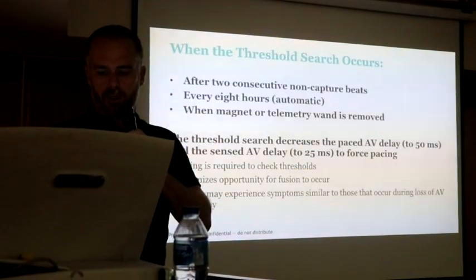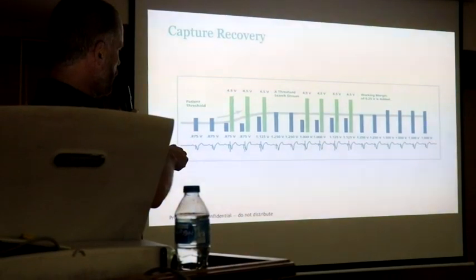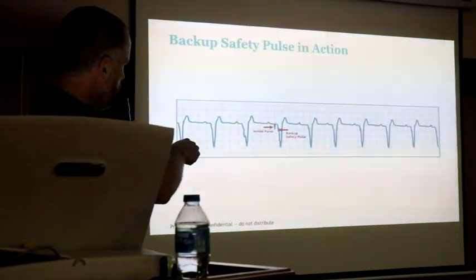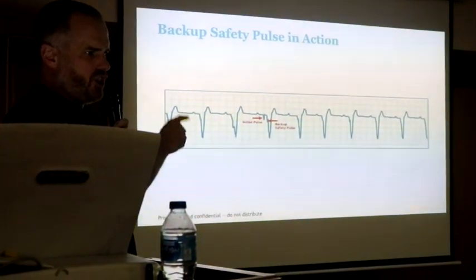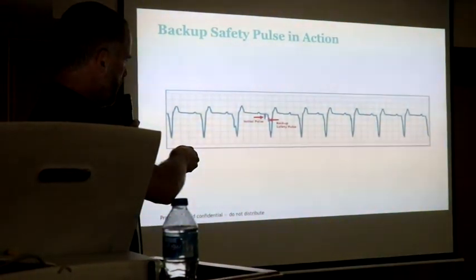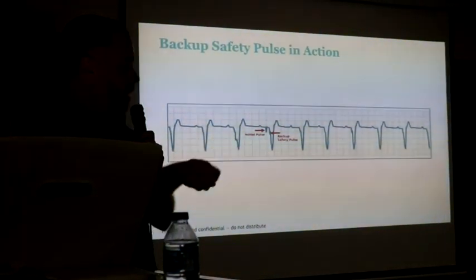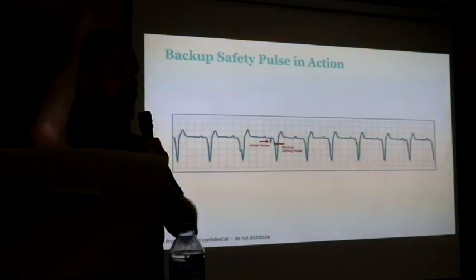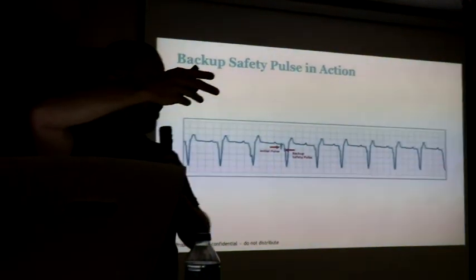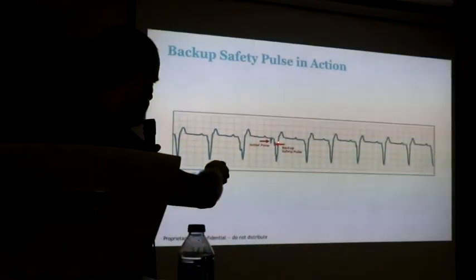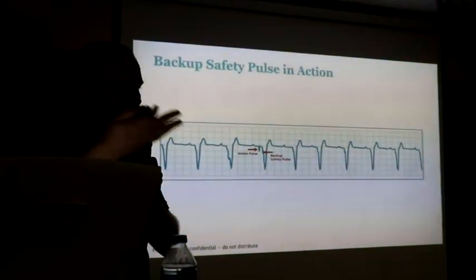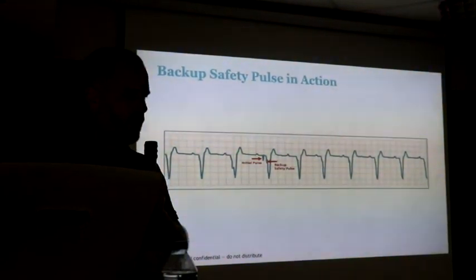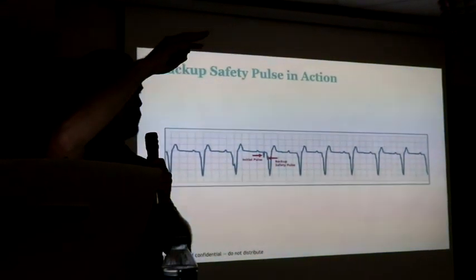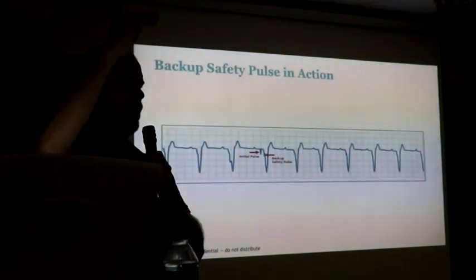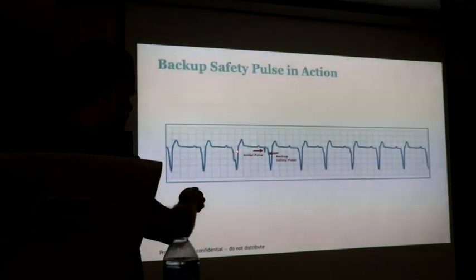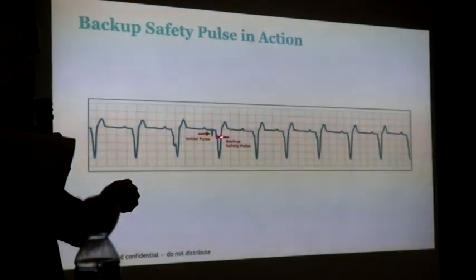So let me come back to this here. We're pacing here at say 1 volt, okay? Threshold is 0.75 and we are pacing at 1 volt. So this pulse here is 1 volt and it fails. The device goes failure, and then it brings in the backup pulse, and the backup pulse is either 4.5 or 5 volts, depending on the device. So this then is 5 volts. That's why your safety margin is 5 volts, right? Because if it fails, it paces at 5. And then it will run a threshold, work out that the threshold has gone up, and then add 0.25 on the threshold. So maybe this patient's threshold was 0.75 here, but was 1.25 at this point here.